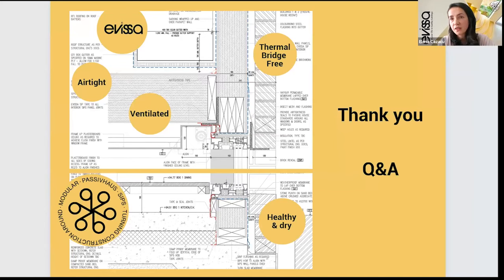Natural ventilation obviously will occur by opening a window and having cross ventilation, with east, west, north, south windows that can be opened concurrently. We have noticed, because we installed indoor air quality sensors in the dwellings we're delivering, that if there's a missed opportunity to install a ventilation system, especially during the night, the carbon dioxide and volatile organic compounds build up to significant levels.